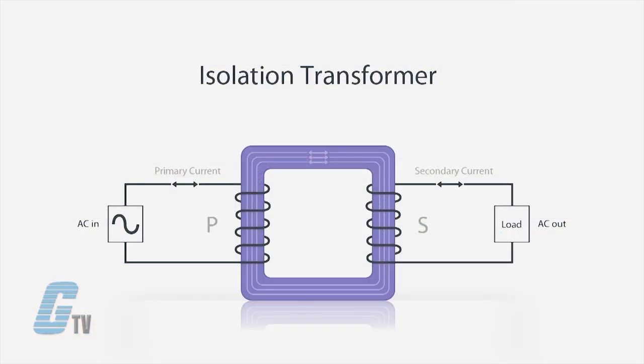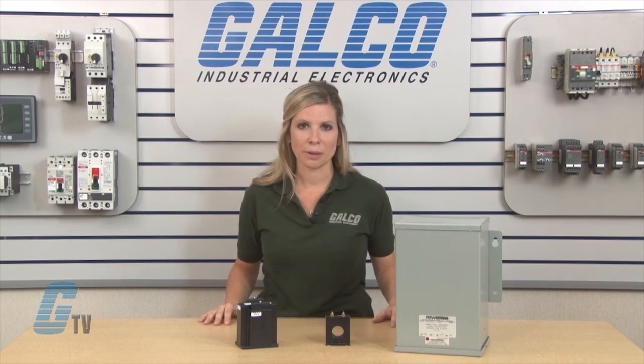An isolation transformer is a very unique transformer. It has a 1 to 1 turns ratio. Therefore, it does not step voltage up or down. Instead, it serves as a safety device. It is used to isolate the grounded conductor of a power line from the chassis or any portion of a circuit load. These transformers' primary purpose is to isolate circuits.